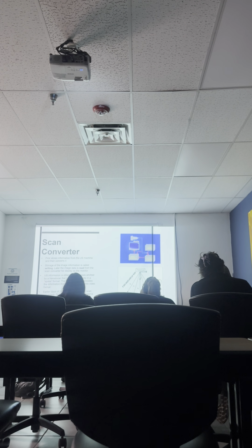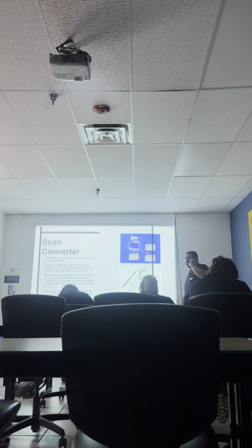So the scan converter first stores information from the ultrasound machine and then converts it. So it doesn't happen instantaneously. The machine needs some time to process the information. So before it loses it, it stores it. It stores it, breaks it down, and then sends it to the display. Everybody get that?